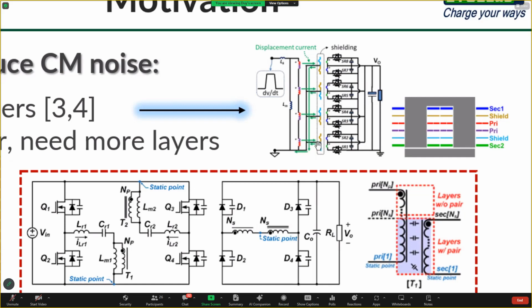When we connect the shielding to the secondary side ground, the gradient voltage of the shielding has to be the same as the primary side winding, so there's no current from the primary side to the shielding, and so there's no common mode noise.